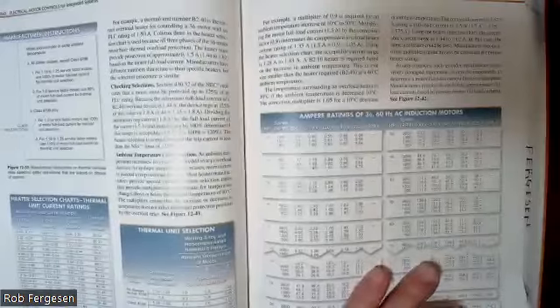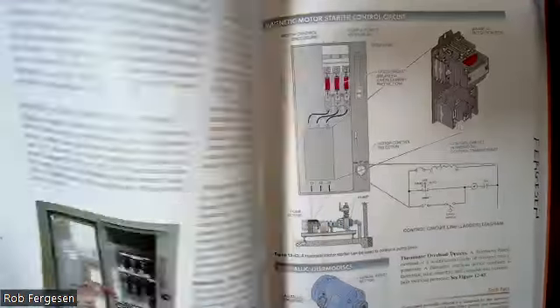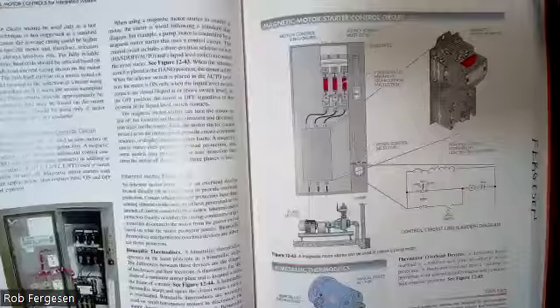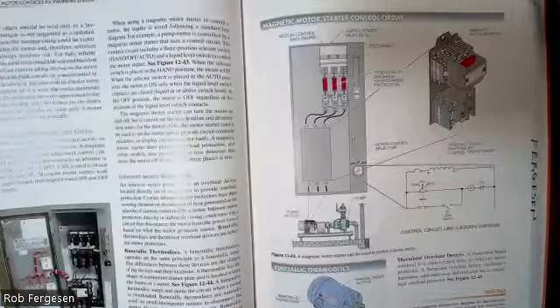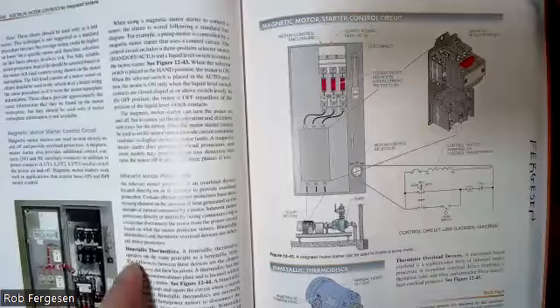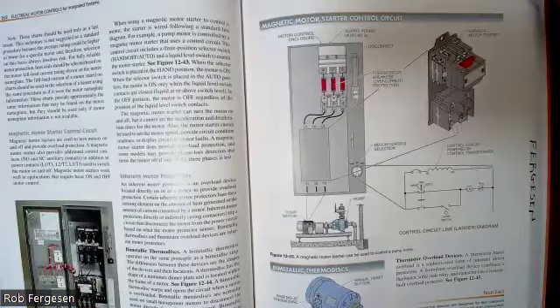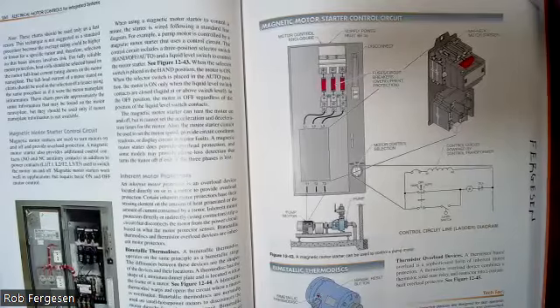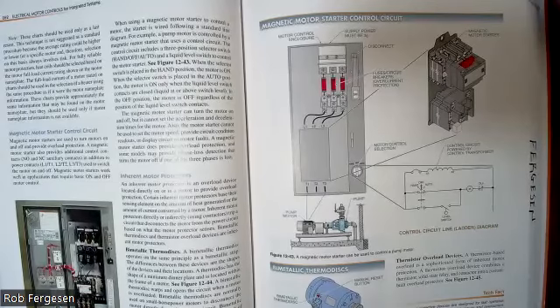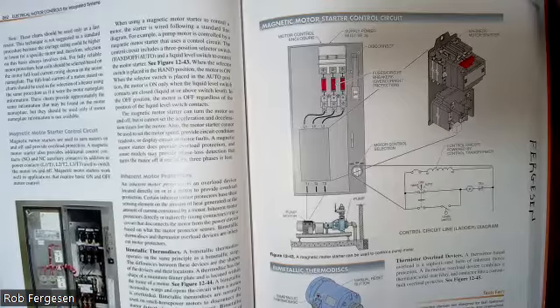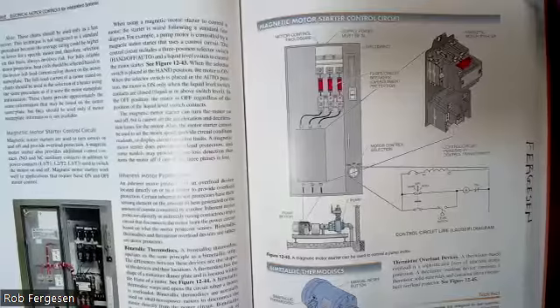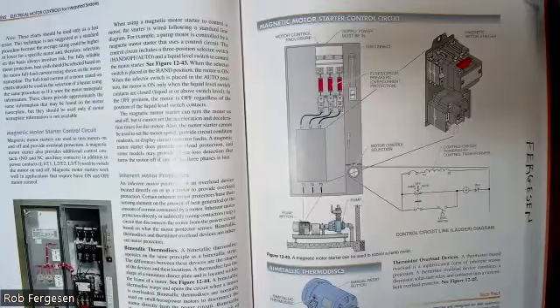And it talks about ambient temperature, like if it gets too hot, you need to size them up slightly. And it shows you some basic motor starter. This is a large system motor starter. Buy it in its own enclosure. It's all set up with the push buttons on the front, pre-wired for you. You can buy them right off the shelf. In our lab, we have this style of manual motor starter that we've got for demonstration purposes.